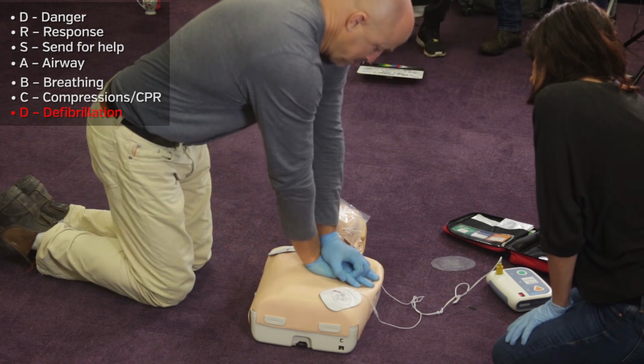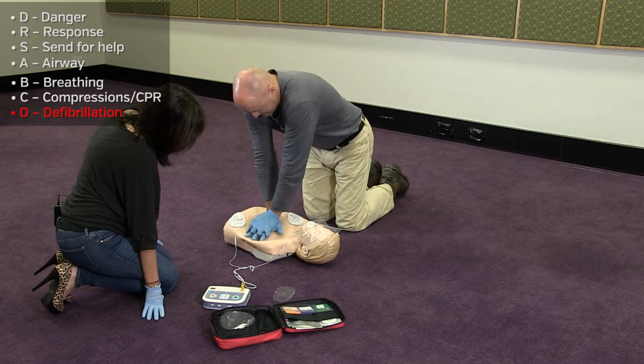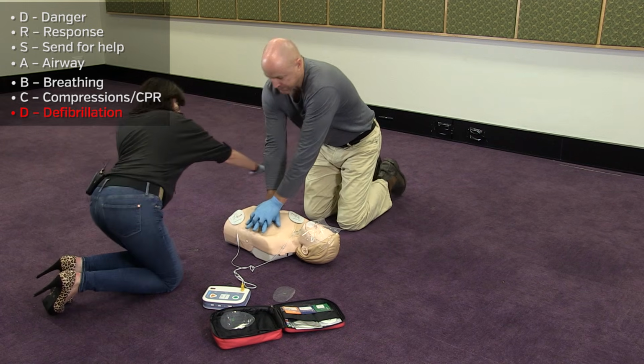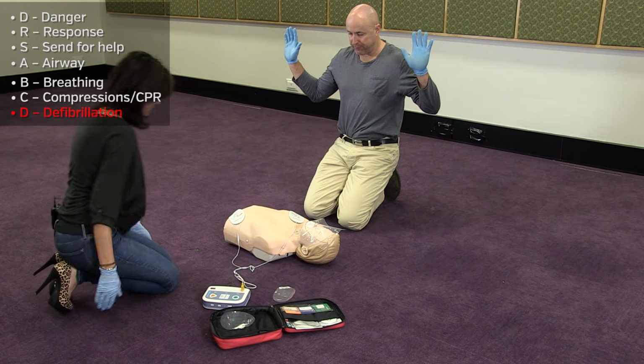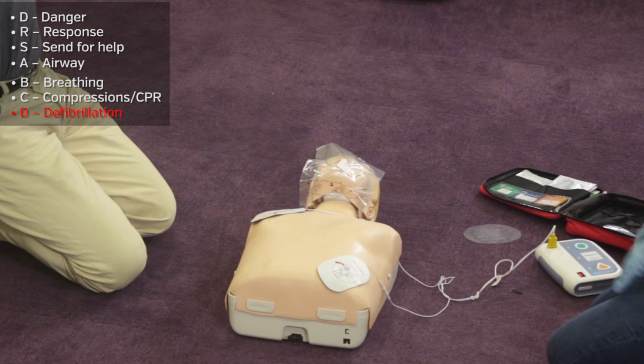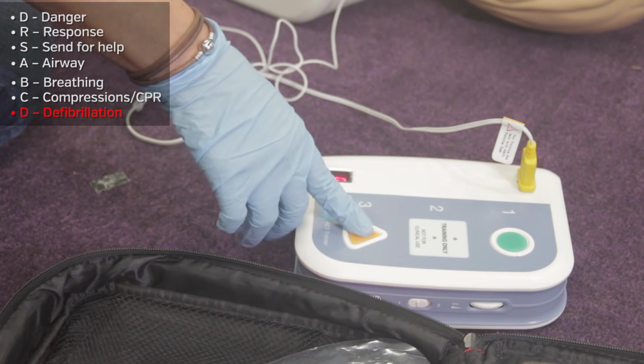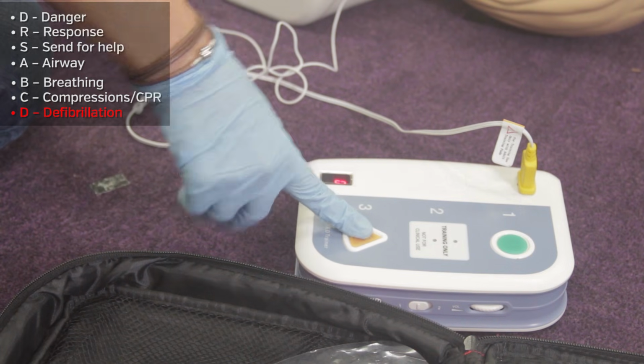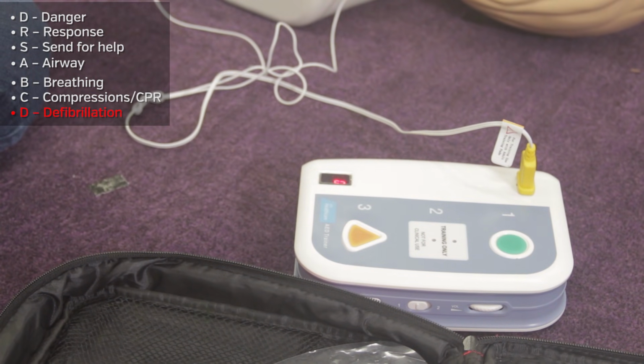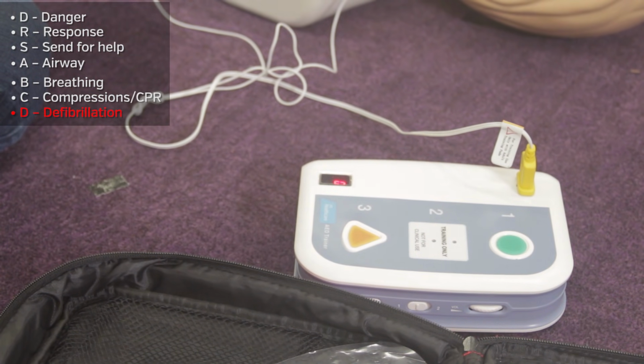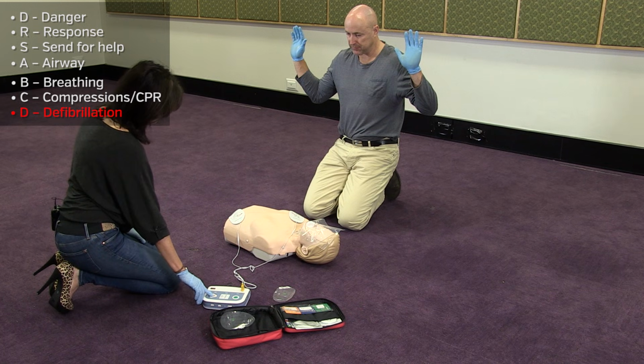Analyzing heart rhythm. Do not touch the patient. Shock advised. Charging. Stay clear of the patient. Stay clear. Deliver shock now.